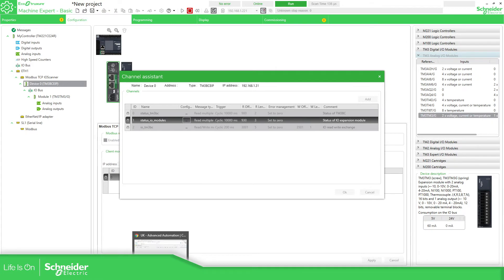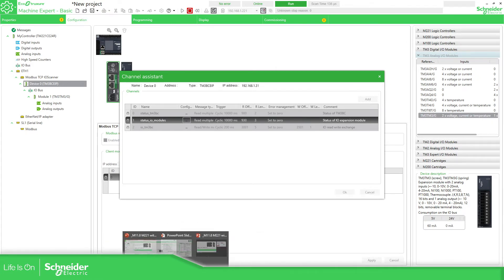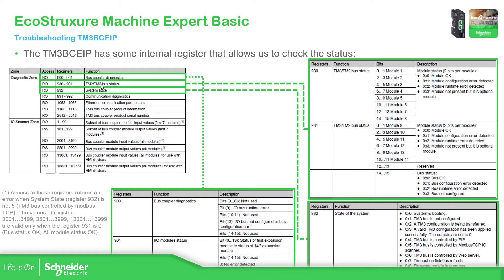If we continue with the presentation, the PLC is reading the bus coupler diagnostic information. You have the register, and you can identify by each bit what's going on. The same can be applied from the status of the registers. Each bit represents one of the modules, and depending on the value it indicates a problem. For each module you have two bits that, depending on the value, tell us if you have any problem or not.